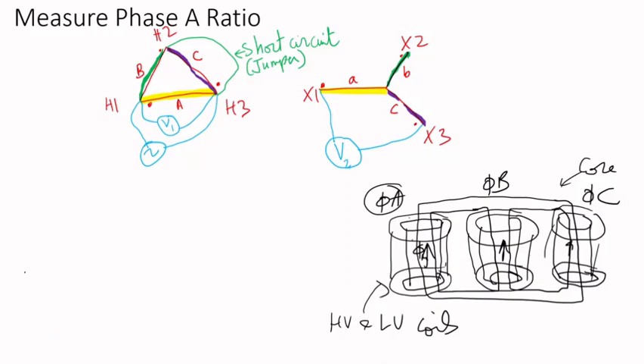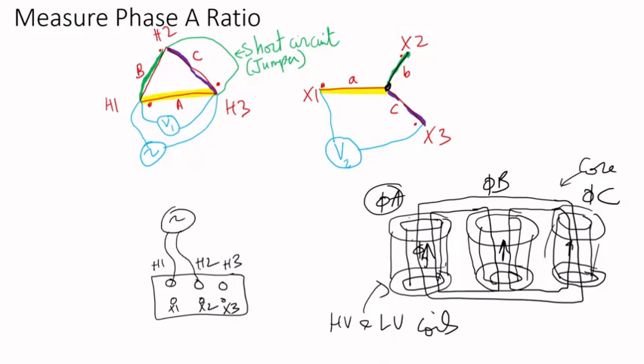Now, if I want to apply the turns ratio, because you see this neutral in the Y here, think about it from the tank. I only have the H1 bushing. If you're looking from the top, H2, and the windings are inside, then I have X1, X2, then X3. So when I measure the turns ratio, I can connect H1 to H2, for instance, then I can measure. This would be the source, but I would also measure the voltage between. That would be, for instance, the voltage measured on the high side, which is basically what was applied minus some voltage drop. Or actually it would be what was applied. Then I'm going to measure the voltage on the other winding.